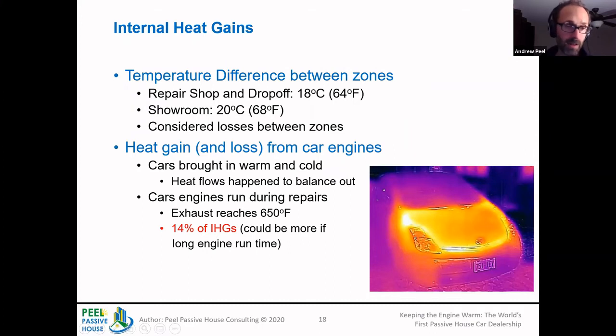And then we also had the car engines running during repairs. After they've repaired it, they may need to turn them on to test them. And the exhaust can actually reach up to 650 Fahrenheit. So very hot. And again, we needed to estimate this. So based on input from the client, we estimated gains. This was based on an estimate of how much they are typically running per service. But it could be noticeably more if they were running longer.